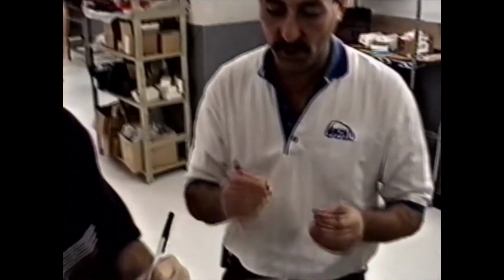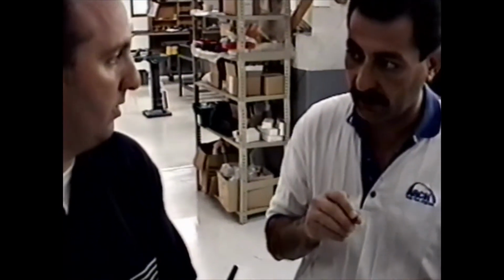That's multiplication, okay. You do the multiplication just to figure out which number you're going to adjust it to. I mean, if this one is far off or both of them are far off, which one do you select? You need to know what to adjust for. At that time you open 5 and 6, leave them open, you go down to the pressure transducer and you adjust with the span.